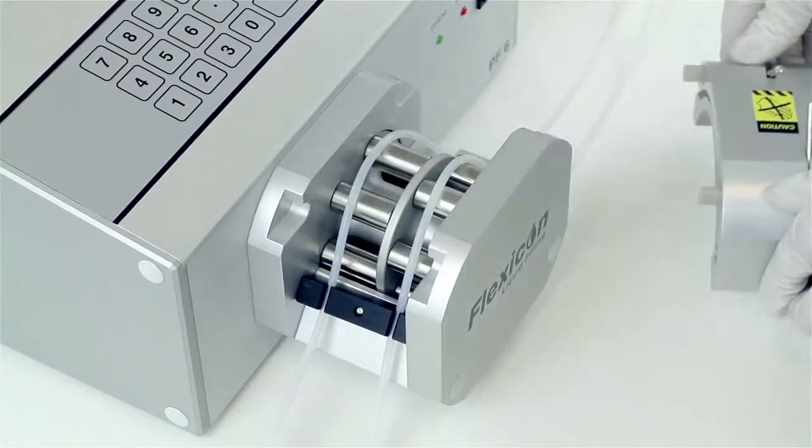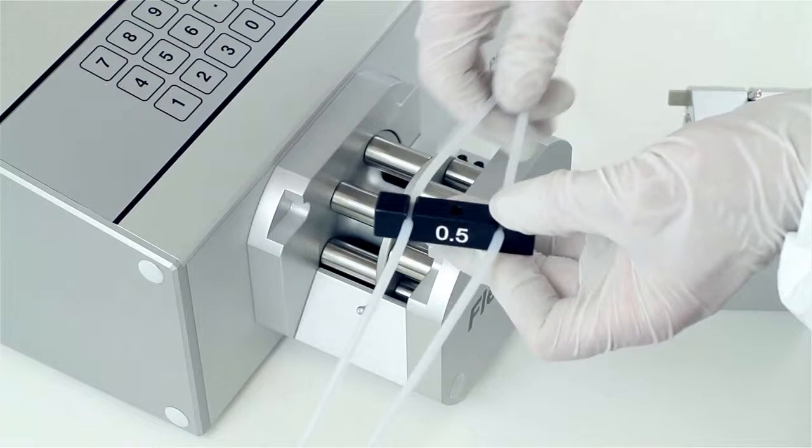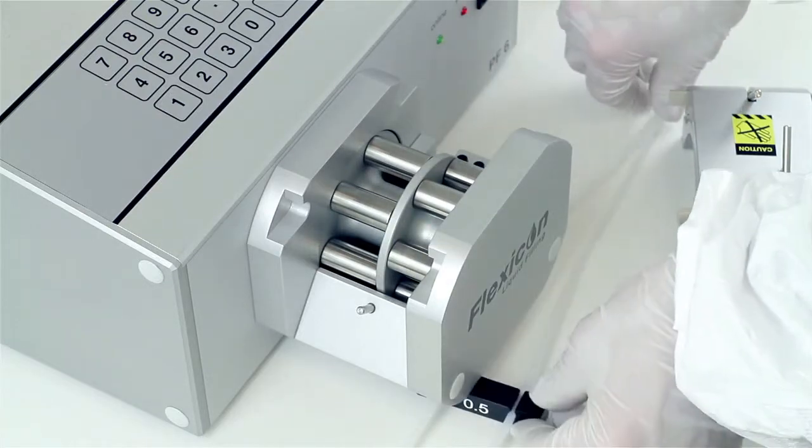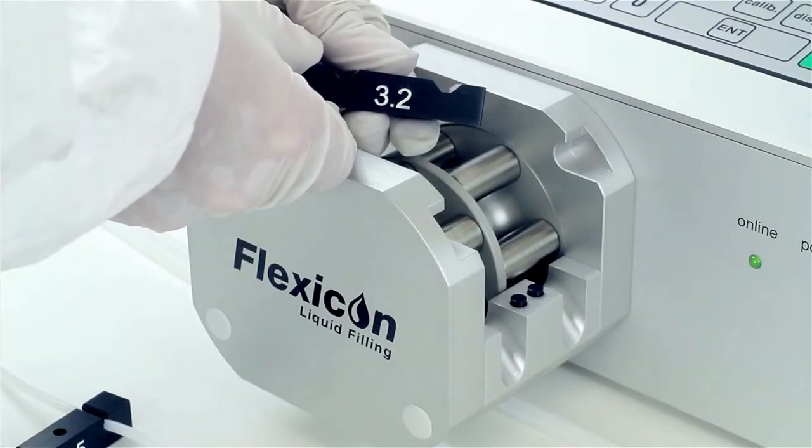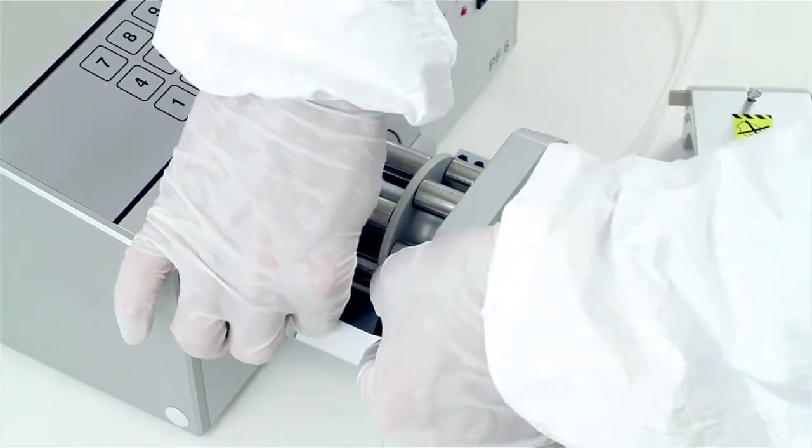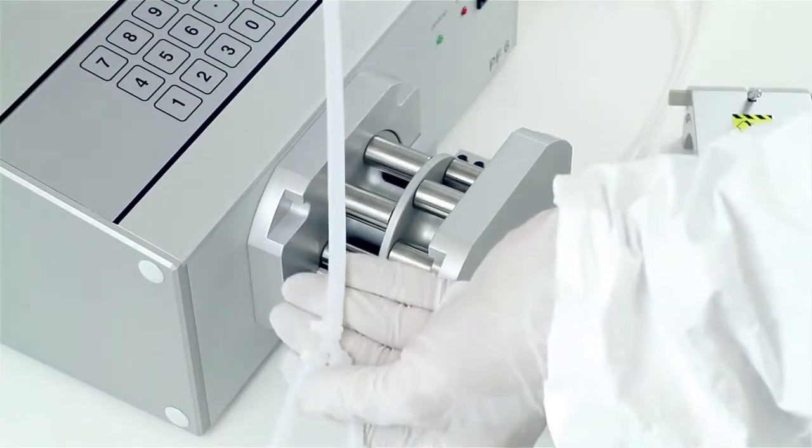When you need to change a fill volume or switch to a different fluid it is not necessary to change the pump head, it is just a matter of changing the tubing or the single-use fluid path assembly. Changing the fluid path can be achieved in under a minute.